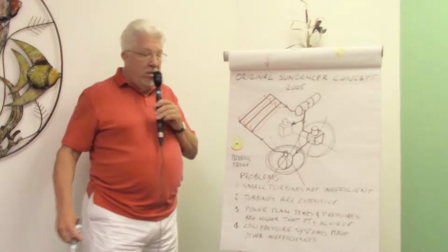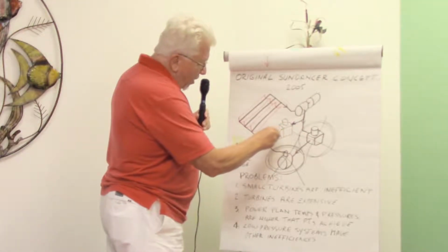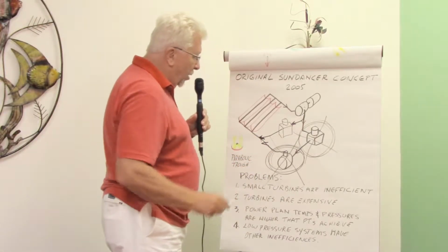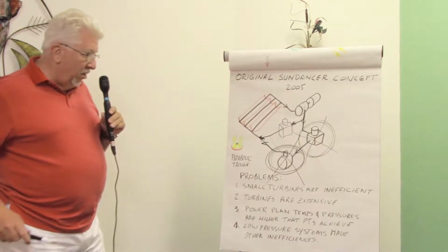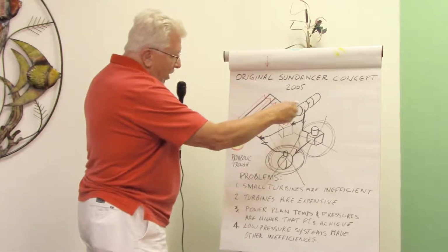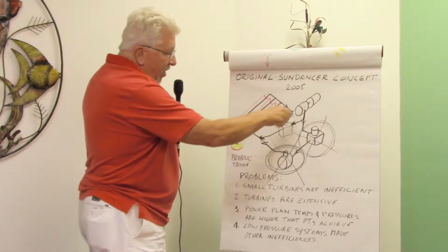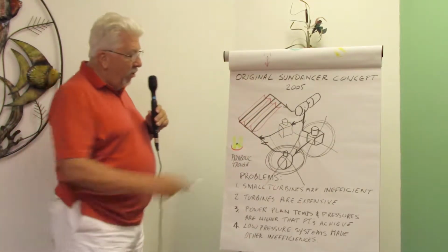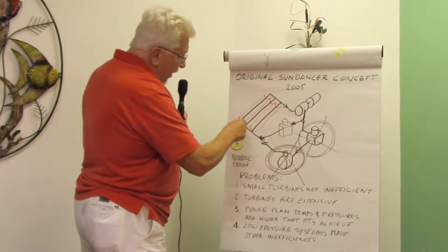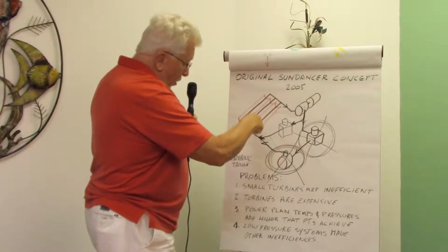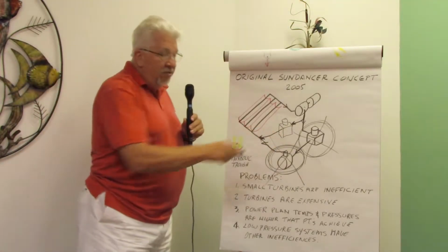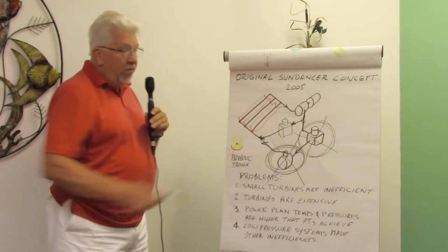and a liquid, okay, and take that and pump it directly back into the system so that the cycle was a little bit different. The cycle was the heat making the steam. The steam goes to a semi-condensing turbine. The biphase exhaust, which is somewhat liquid and somewhat vapor, goes directly to a special pump, and that special pump pumps it directly back into the array, the parabolic trough array. So the cycle then does not have a condenser, and the boiler feed pump is different.